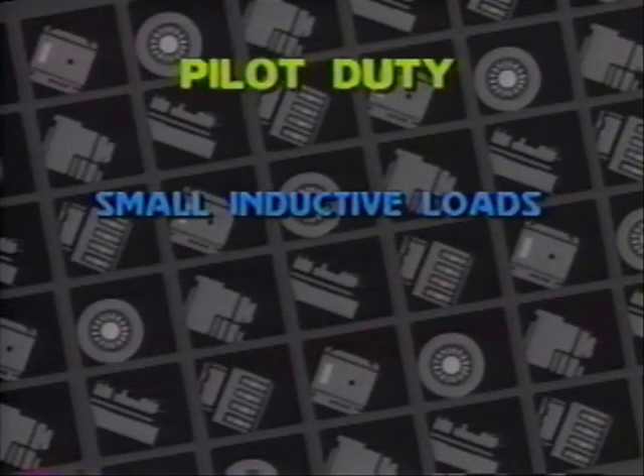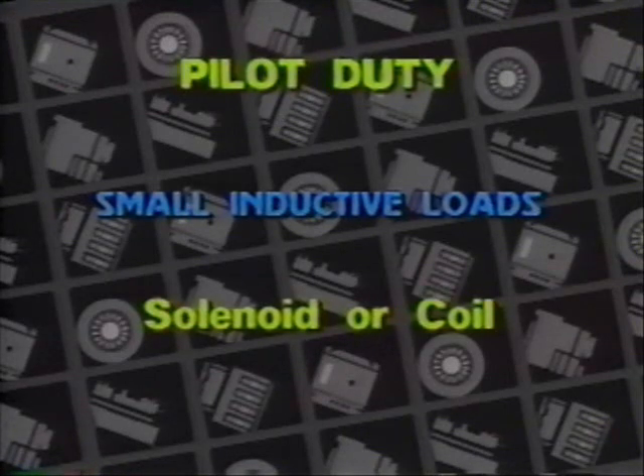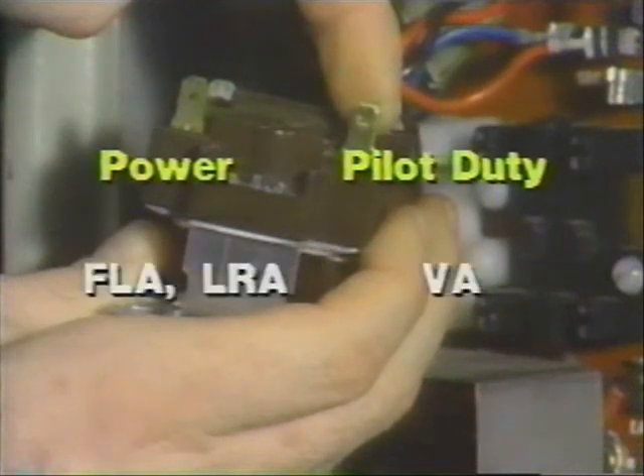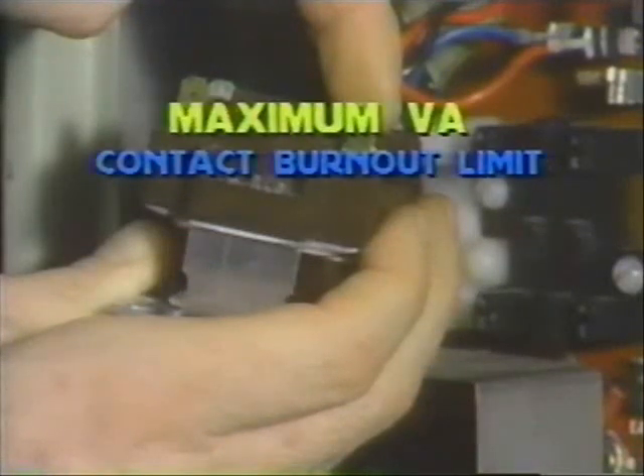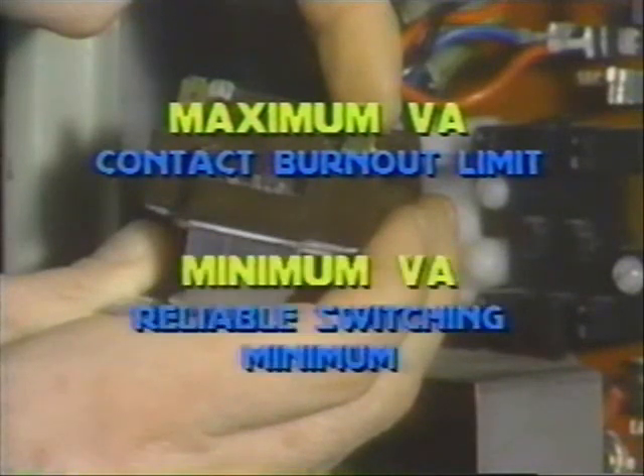Pilot duty is a rating applied to very small inductive loads, usually solenoid or coil, with a top power factor of 40%. Some Honeywell relays have both power poles and pilot duty poles. Power poles are rated in full load and locked rotor, and pilot duty poles are usually rated in maximum and minimum VA. Maximum VA is the most the contacts can handle without burning out prematurely. Minimum VA is the lowest power that can be reliably switched. Minimum on pilot duty contacts is usually about 3 VA.